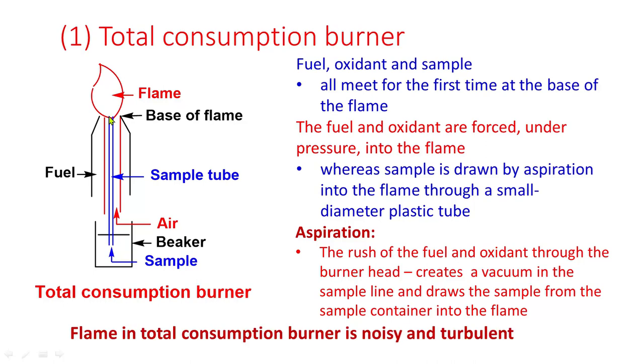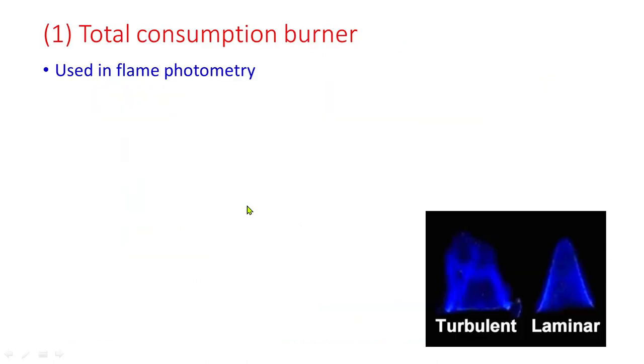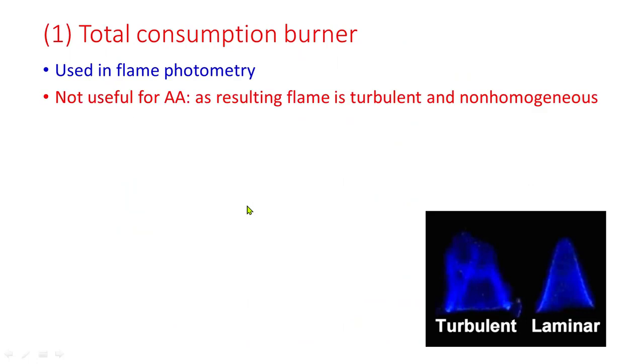The flame in the total consumption burner is noisy and turbulent — sometimes smaller drops, sometimes bigger drops enter the flame. The total consumption burner is used in flame photometry but is not useful for atomic absorption, as the resulting flame is turbulent and non-homogeneous.